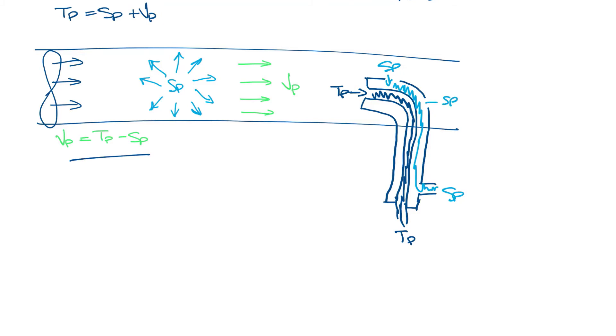Velocity pressure is important because knowing the velocity pressure allows us to calculate the velocity. So the equation for velocity is velocity equals 4005 times the square root of velocity pressure. And if we know the velocity and the area of the ductwork, we can calculate air flow because the equation for air flow is CFM equals area times velocity.